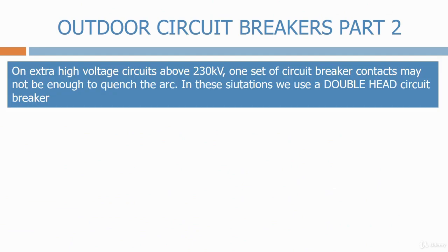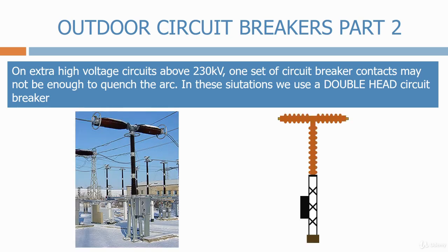On extra high voltage circuits above 230 kV, one set of circuit breaker contacts may not be enough to quench the arc. In these situations, we use a double head circuit breaker. These have duplicated arcing chambers, one in each horizontal leg, both operated from the same mechanism. Let's look inside the circuit breaker to see how that works in practice.